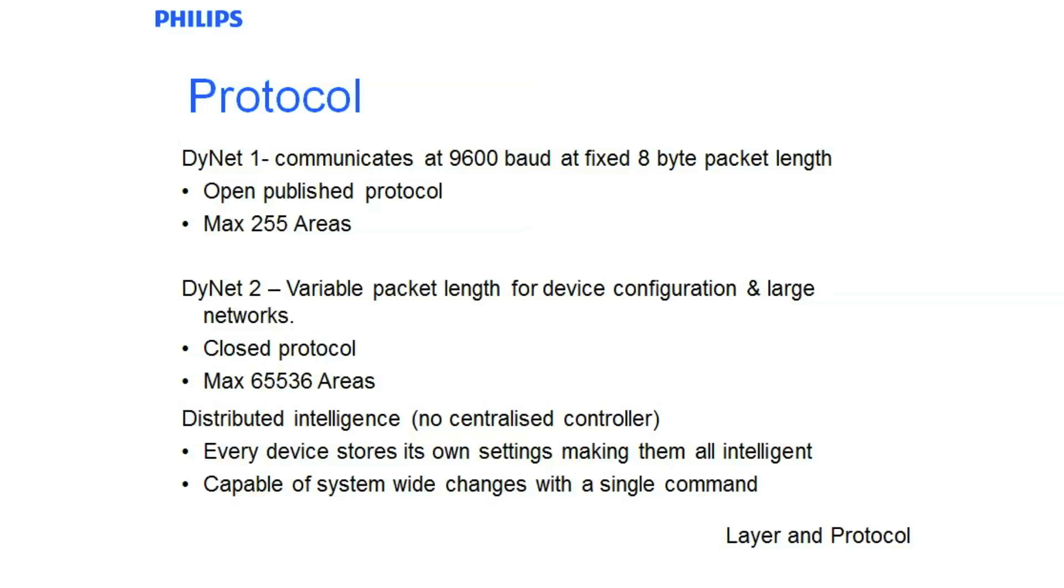DyNet 2. With the advent of a lot of large buildings in modern day, it has required the need for DyNet 2. DyNet 2 is basically a variable packet length for device configuration and large networks. Typically the modern day software applications that are used by Philips Dynalite use DyNet 2 as a way to upload and download data between the software and devices. DyNet 2 is also used in large network systems where we run a DyNet 2 backbone down the trunks of large buildings and then we run DyNet 1 spurs on a per floor basis. This allows for a really good trunk and spur topology where we can put offsets on each floor and then have independent floor control but still global control from anywhere on the trunk.